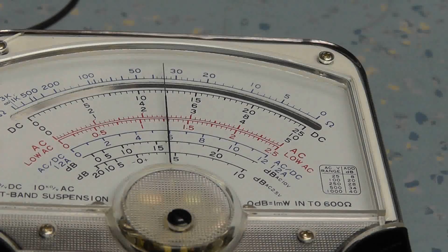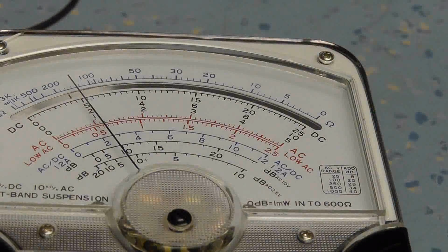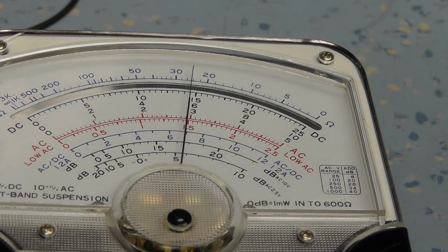We're slightly off. Let's try it on the 25 volt range. Let's give it say 15 volts. Okay, so that's about 15. There's 15 volts there. Similar sort of thing, slightly off. So it's looking like the calibration that needs to be done, if any, which I probably won't bother with, is the main calibration post the selectable attenuator, actually up by the meter section. And I think there is a variable resistor for adjusting that.